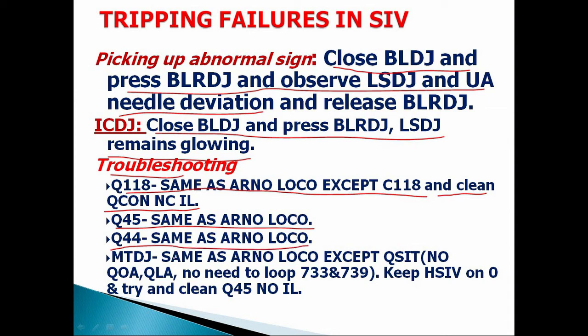Coming to the second part, second branch of the DJ circuit, troubleshooting procedure for Q45 is same, and troubleshooting procedure for Q44 is also same. But for MTDJ branch, almost everything is same except QSIT. So if QSIT is energized, after resetting QSIT only, he shall close DJ. And there is no need of looping 733 and 739 wires since there is no normally open interlock of C118. That is for MTDJ, he has to reset all safety relays targets. Locopilot has to keep HQOB 1 and 2 in opposition and try, and Locopilot has to tap QPDJ, increase RS pressure, and if still unsuccessful, Locopilot shall keep HSIV on 0 and clean Q45 NO interlock also to overcome the trouble for MTDJ branch de-energization.